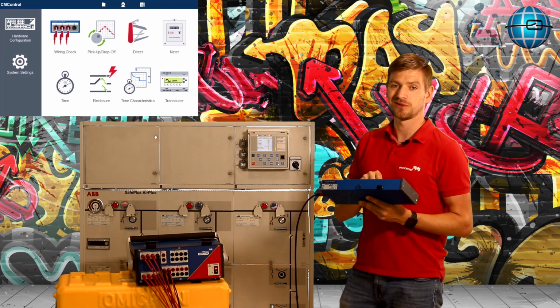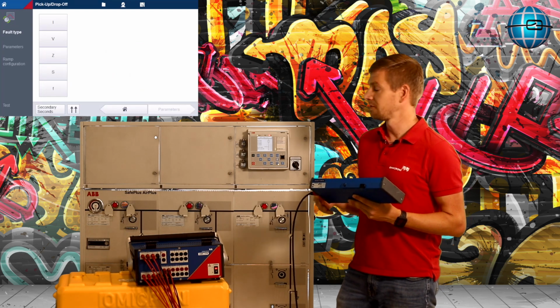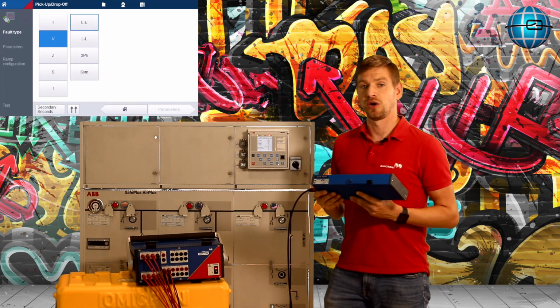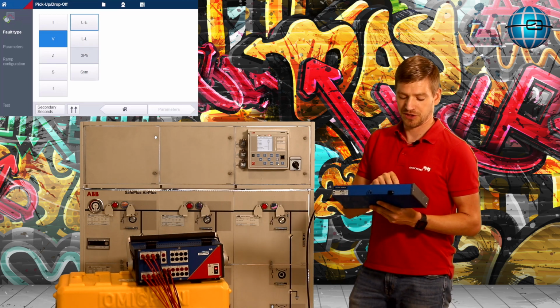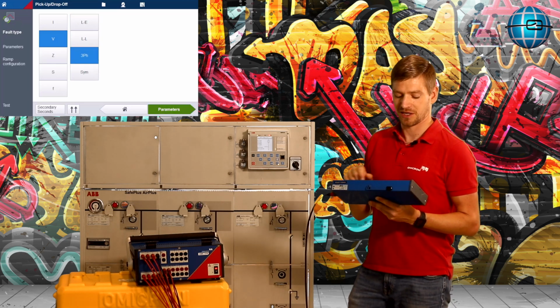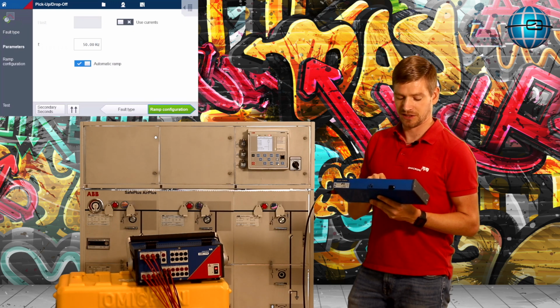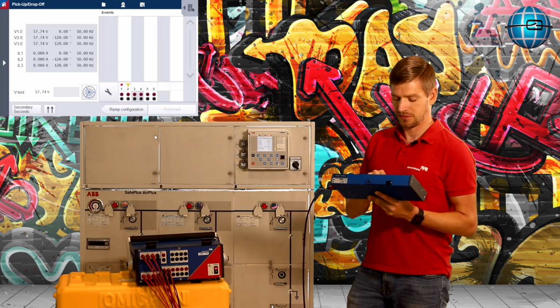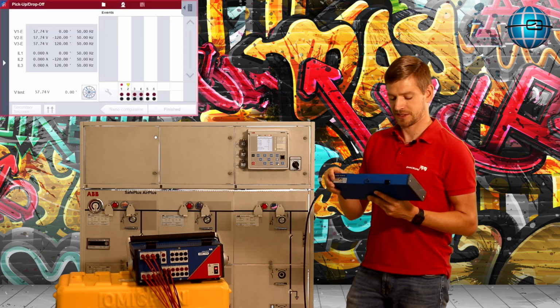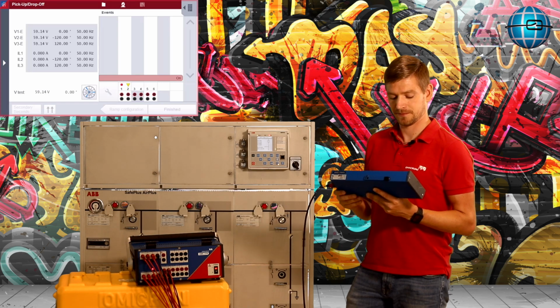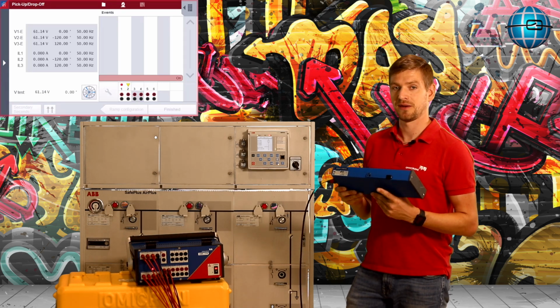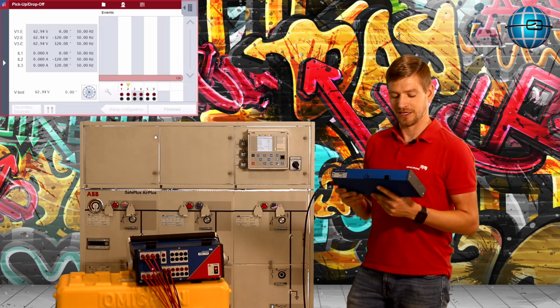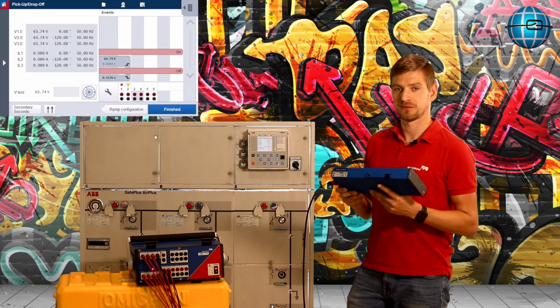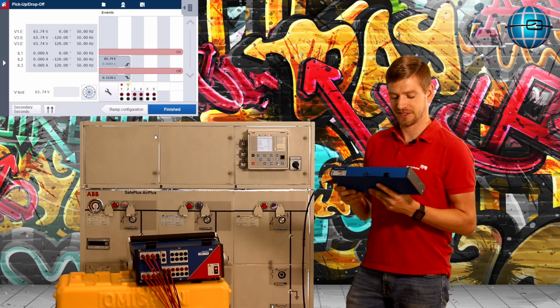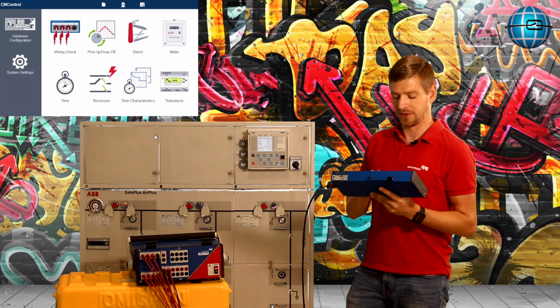So let's do this also again for the voltage. We have configured here an overvoltage protection of 1.1 of nominal voltage. And we do the same as before with current. We go up here with the voltage signal, also use this automatic ramp, and here start the test. So CM control again raises the voltage, and now let's wait for the overvoltage pickup. Okay, here it is. So exactly as we configured.